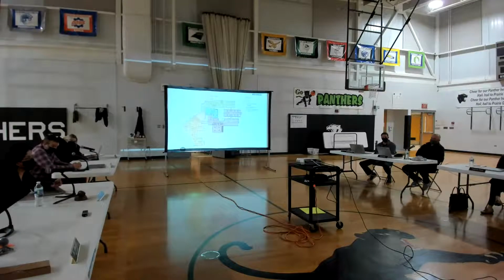Yes, that's correct. The other question I have about geothermal, although I don't completely understand how it works, is that I know you can drill down 200, 300 feet into the ground. Does that disturb the water table? We're very sensitive in this area about our water. No, it's what's called a closed loop system, so we're not using the water in the ground at all. They drill the tubes and grout them, surrounding them with grout all the way down, so it's a closed loop system. The refrigerant, or the water with a refrigerant constitution, flows through pipes surrounded by concrete, so they're not connected to any groundwater source and don't disturb it.